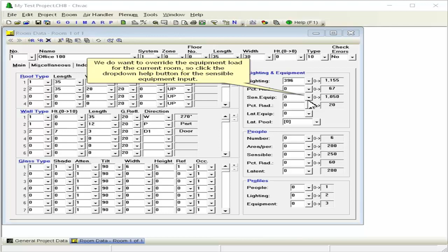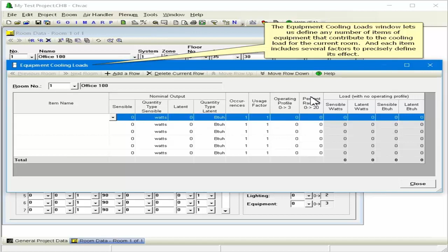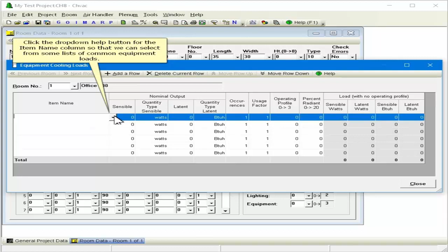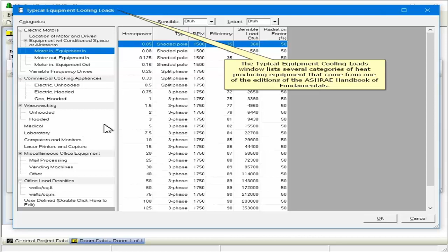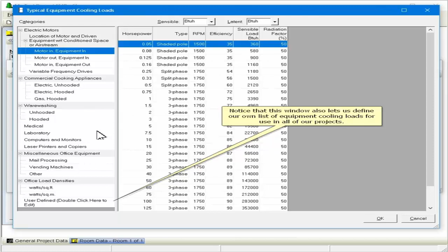The Equipment Cooling Loads window lets us define any number of items of equipment that contribute to the cooling load for the current room. And each item includes several factors to precisely define its effect. Click the drop-down Help button for the Item Name column so that we can select from some lists of common equipment loads. The typical Equipment Cooling Loads window lists several categories of heat-producing equipment that come from one of the editions of the ASHRAE Handbook of Fundamentals. Notice that this window also lets us define our own list of equipment cooling loads for use in all of our projects.